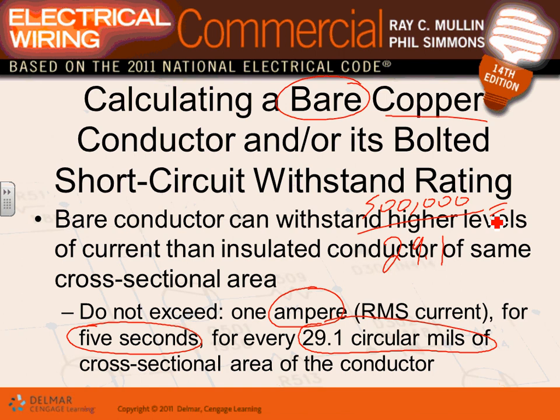Gentlemen, that will get you how much current this conductor can handle for 5 seconds. If you want it for 1 second, what do you do? Flip the formula again. It will get you how much it can handle for 1 second. Do you guys expect it to handle more for 1 second than for 5 seconds? Yep. For 1 second, the conductor will withstand, hold more current than for 5 seconds. How about for 10 seconds? Less. The more time, the less current the conductor can handle because you are being baked and shaken. The longer you let that food be shaken and baked, the more you're going to damage it. That's how you find it if it's a bare conductor.